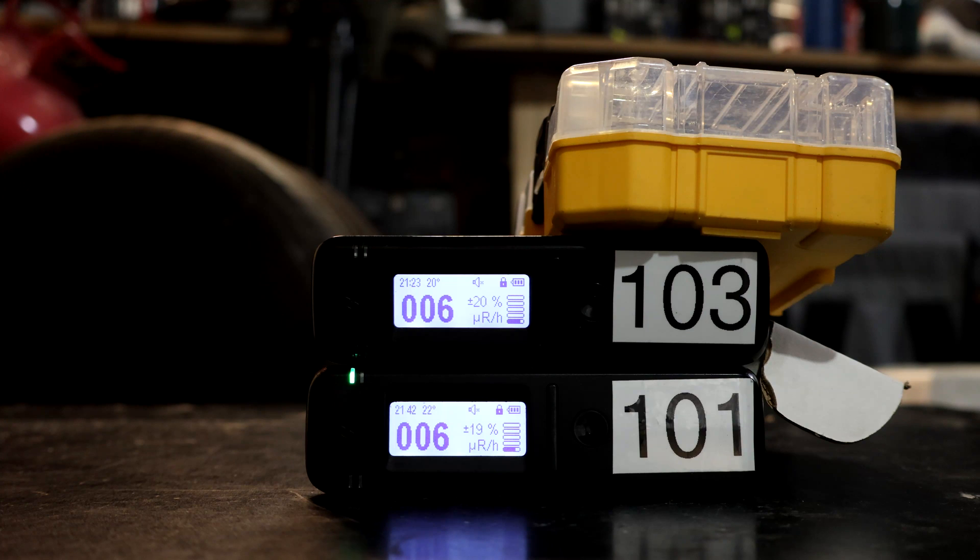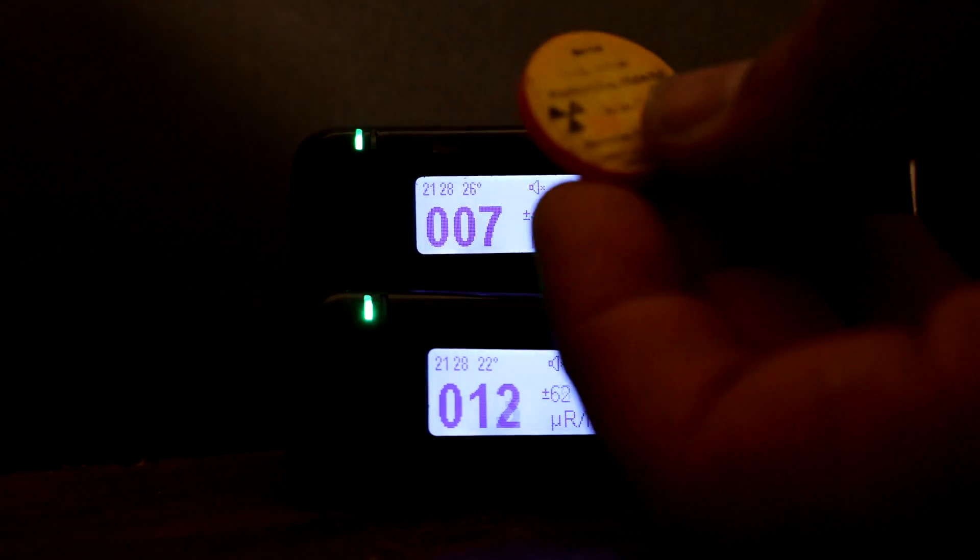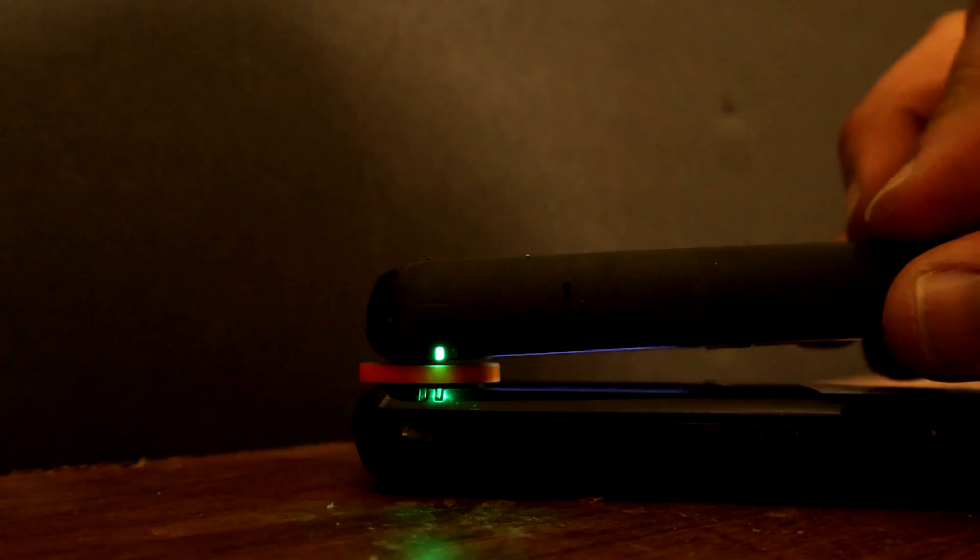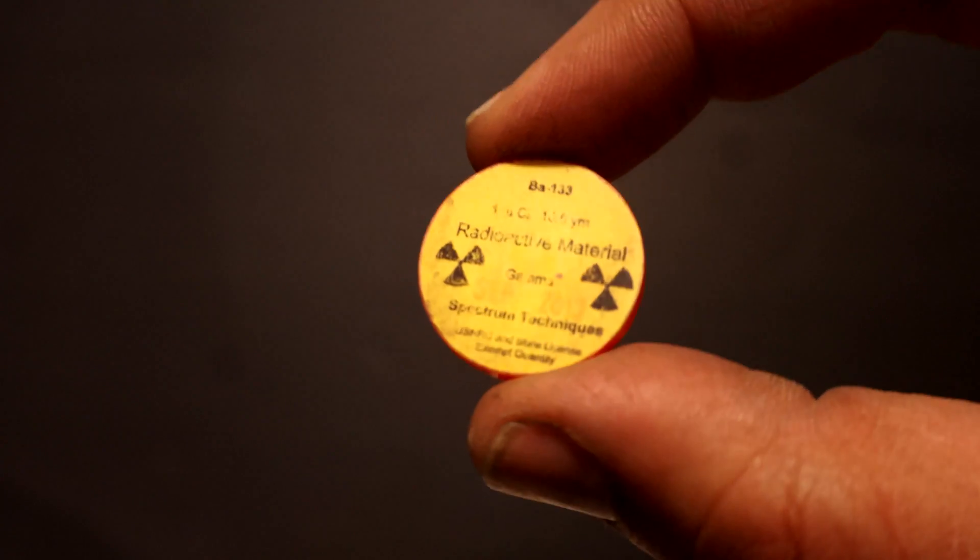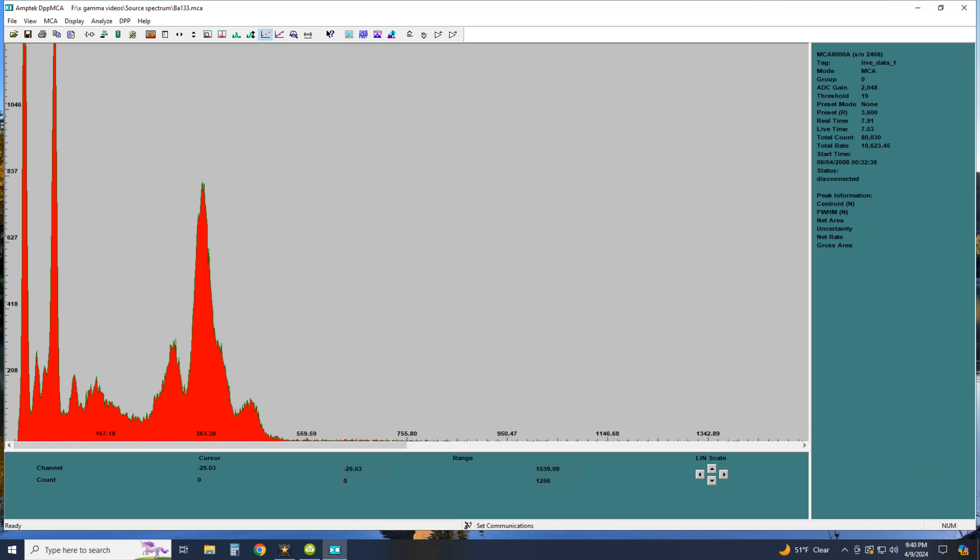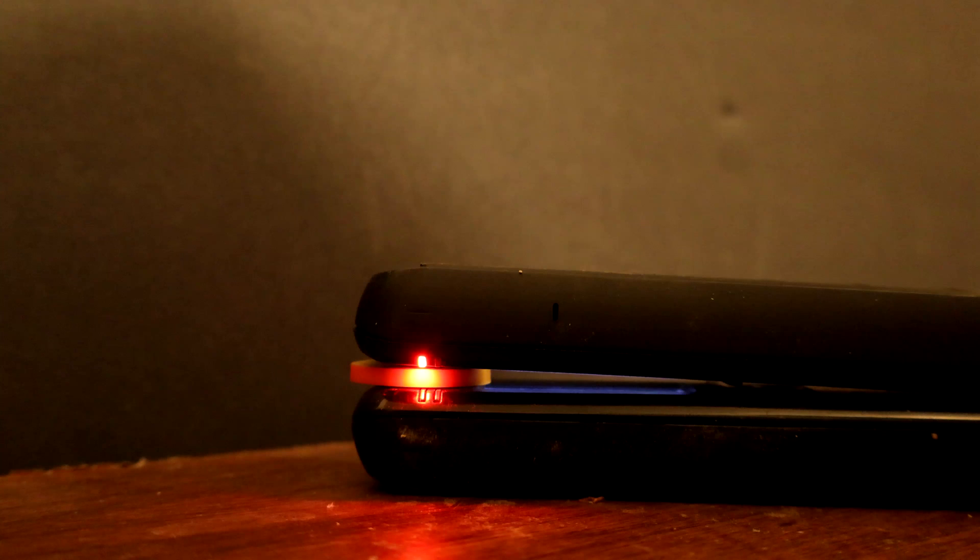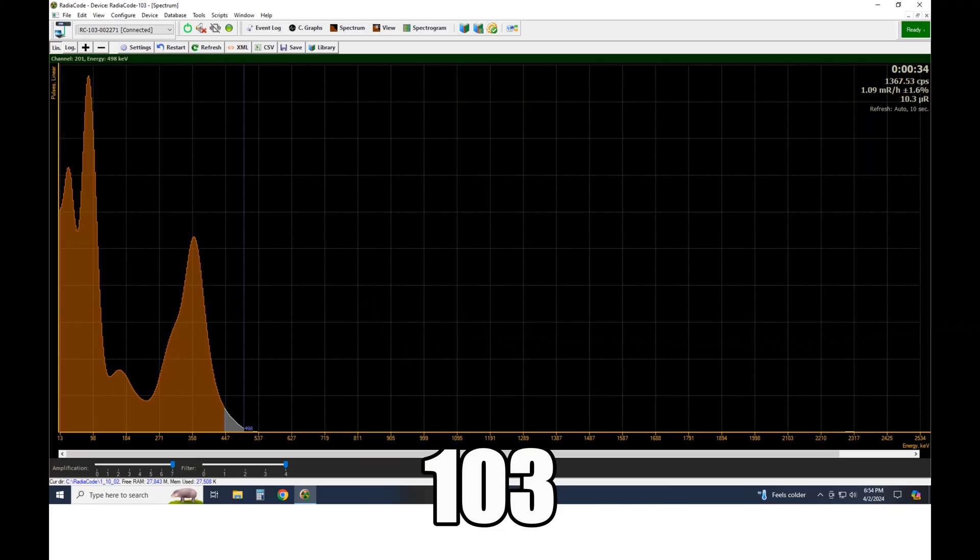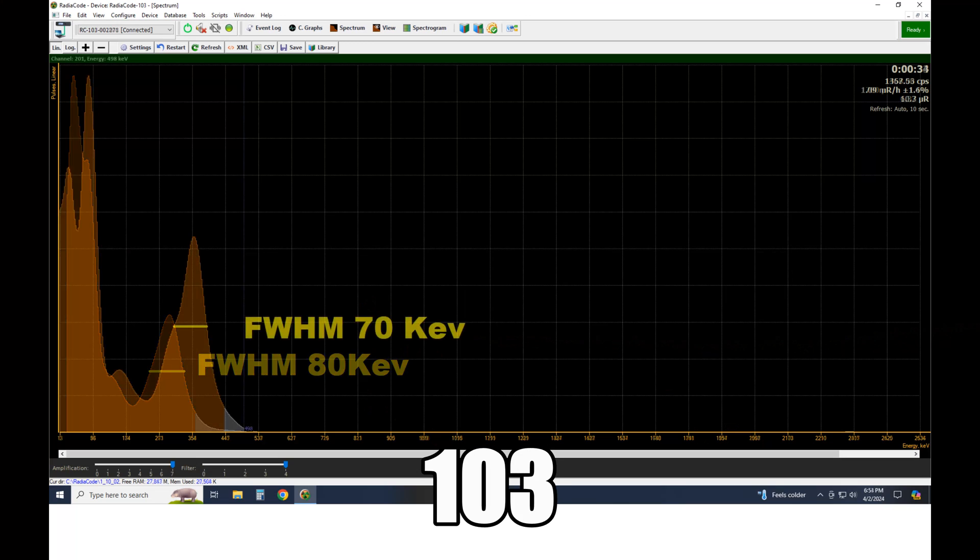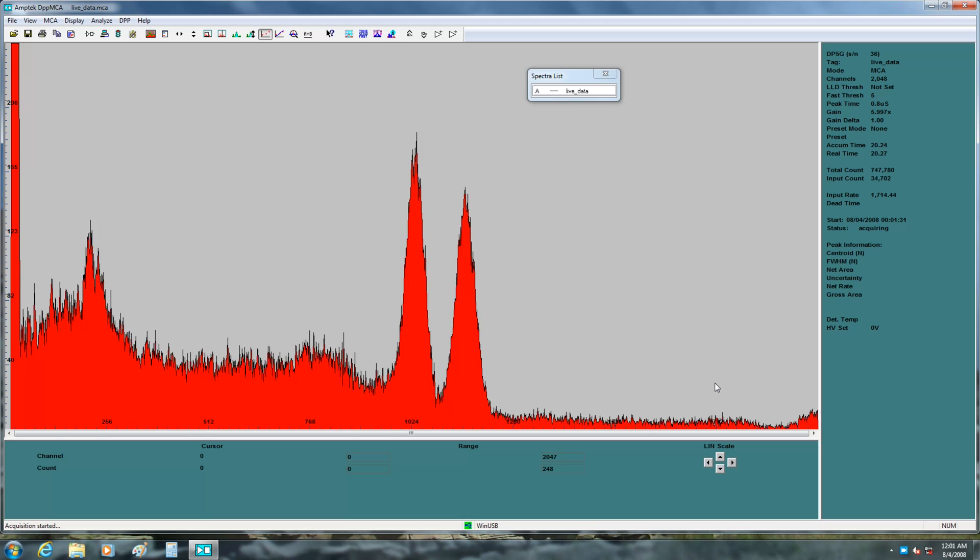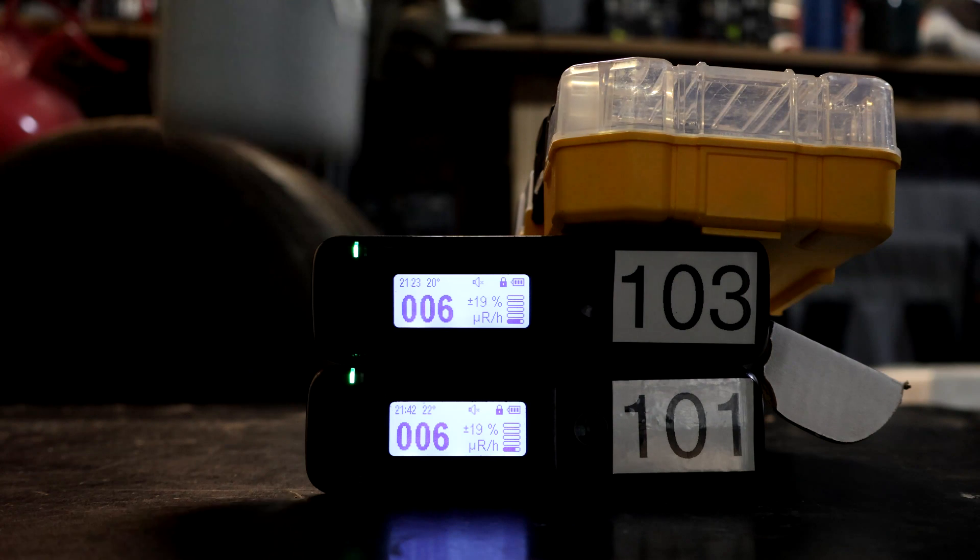What does it actually mean? Let's take a look at this 32-second acquisition of this 11-year-old 1-microcurie source of Ba-133, specifically the peak at 356 keV here. In the same time it takes to collect the spectrum with the 101, the 103 gathers more data and the peak is higher. If we compare each peak at half maximum, the 103 yields a slightly more narrow peak. Why should we care? A higher resolution is beneficial when identifying two peaks close to each other.